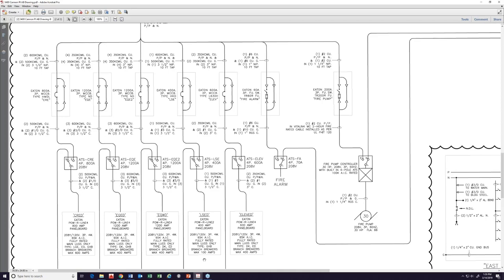And this way I have all my branch circuits in each of these two panel boards, but I don't have one panel board being a sub panel from another. They are both 400 amp rated panel boards. That also makes it a better system, a more reliable system. The only downside to that is that I have to have a 400 amp feeder. If you want to get around that, you have two options. Either I can size this up to a 600 such as this one, but now you're spending more money for a larger disconnect, larger circuit breaker, a larger ATS, which I'd rather not do.